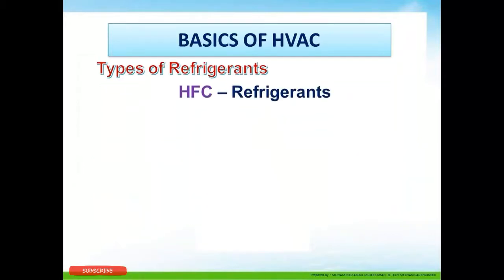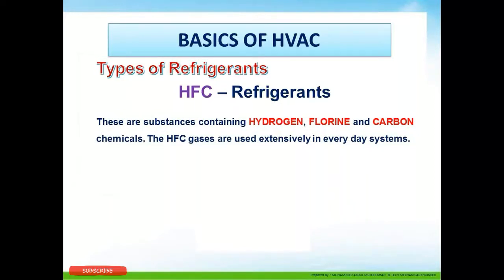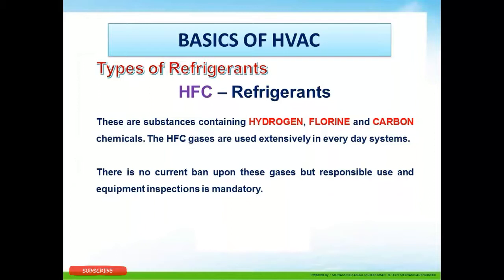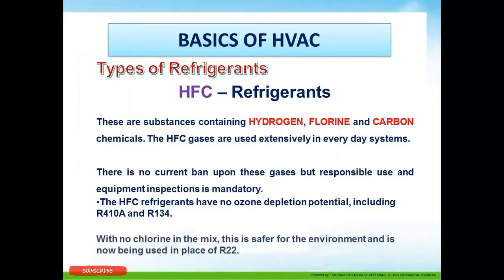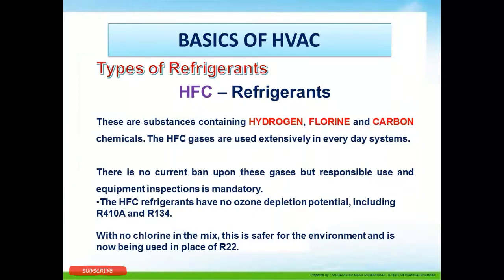HFC refrigerants are substances containing hydrogen, fluorine, and carbon chemicals. HFC gases are used extensively in everyday systems. There is no current ban on these gases, but responsible use and equipment inspection is mandatory. HFC refrigerants including R410A and R134A have no ozone depletion potential because there is no chlorine in the mix, making them safer for the environment and the current replacement for R22.